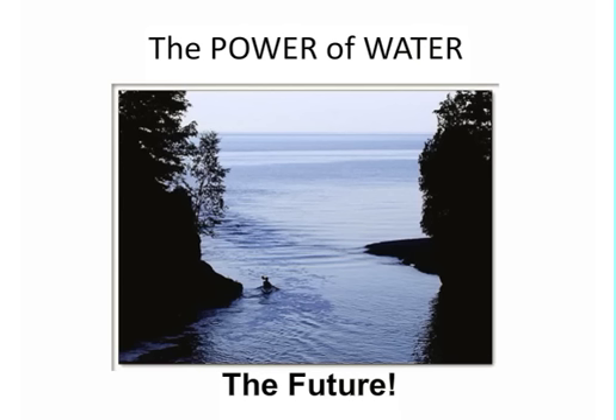So again, when you have a body of water that has the surface area, the depth, and you have good access within that distance we've talked about, and you size, design, and install it correctly so that you're utilizing the water flow of that body through the heat exchange surface area you've applied, it is a terrific source.